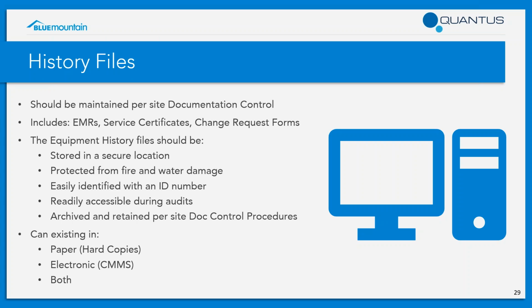So coming into history files, as you know, proper storage of these files is really critical to your process. As you're defining them within your master program SOP, you want to be careful not to conflict with other site documentation control procedures. Typical outputs of this are going to be your equipment master records, service records or certificates, and some customers will use a change request form that they'll file with the instrument if they're using that to update intervals or tolerances. These history files should obviously be stored in a secure location that's protected from fire or water damage if you're storing a hard copy. They should be easily identified with an ID number and readily accessible during audits.